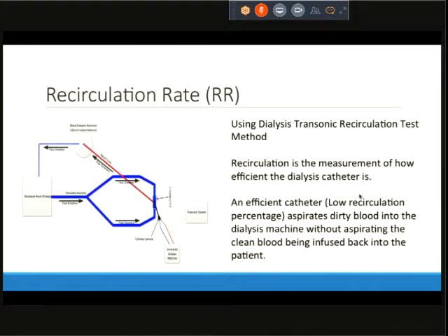The third test we did was the recirculation rate. Basically using the dialysis transonic recirculation test method, as you can see on the left side, from the simulator, this overall flow directed this way around towards the glycerin water mixture down back to the simulator heart is the normal circulation we're simulating. And here's the catheter insertion portion.